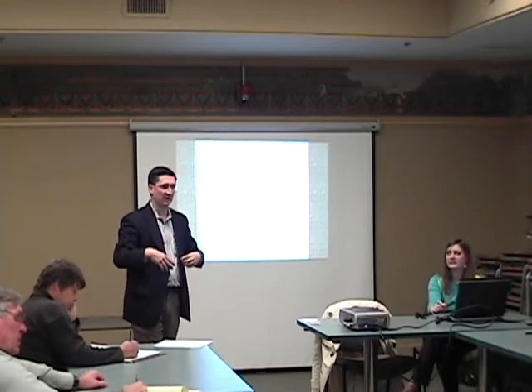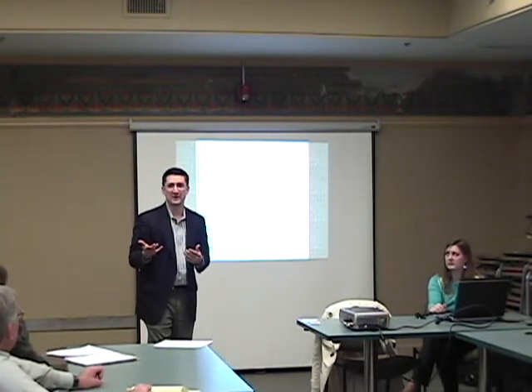impactful in doing sustainable design. If you do a normal, anybody here a mechanical engineer? All right, what's the normal amount of tonnage per square foot? So for an office structure, it's like 350 square feet per ton. Right, usually about 350, 400. Okay. We have 12,000 square feet that we're dealing with, so we're at 30 tons of air conditioning. We have 15.